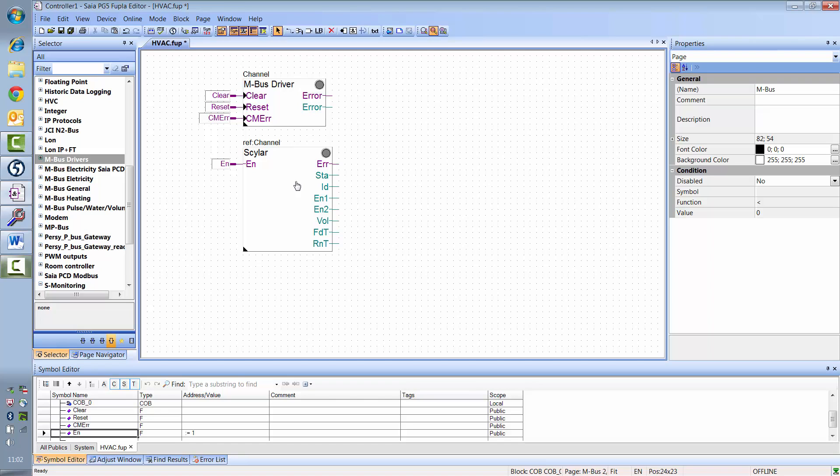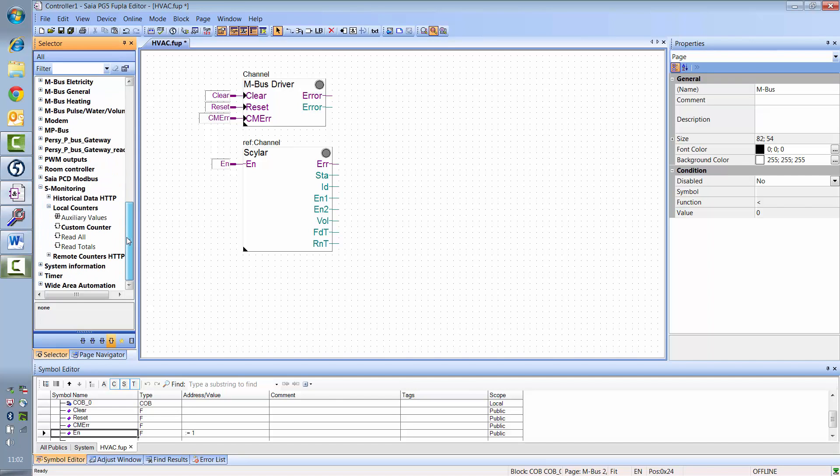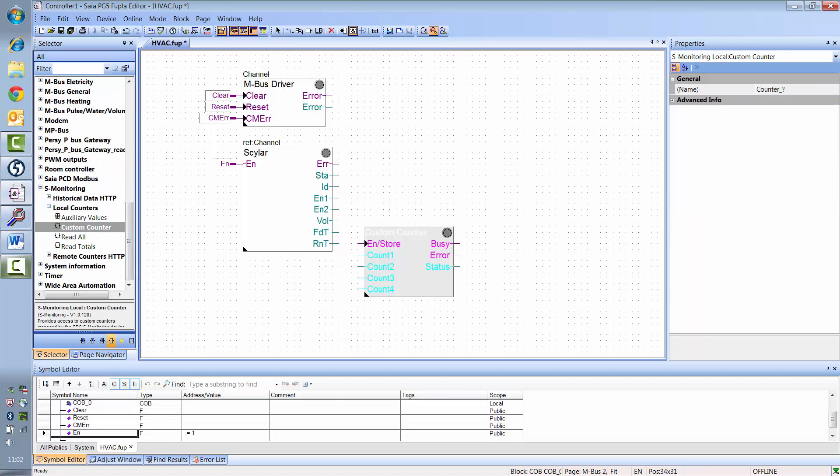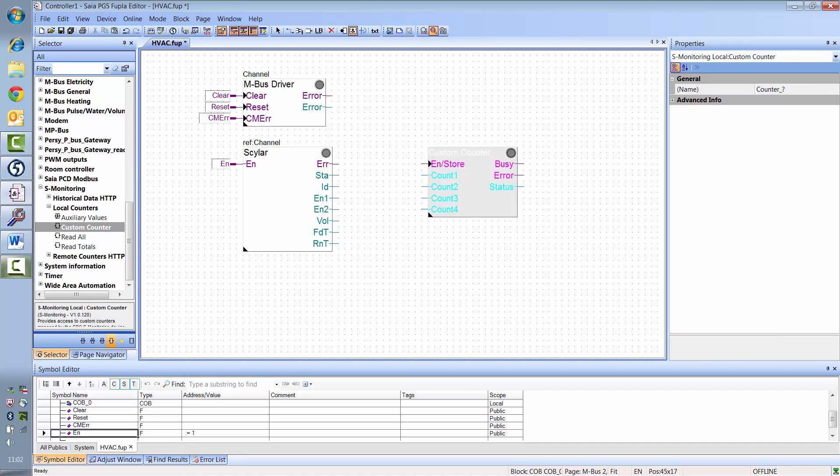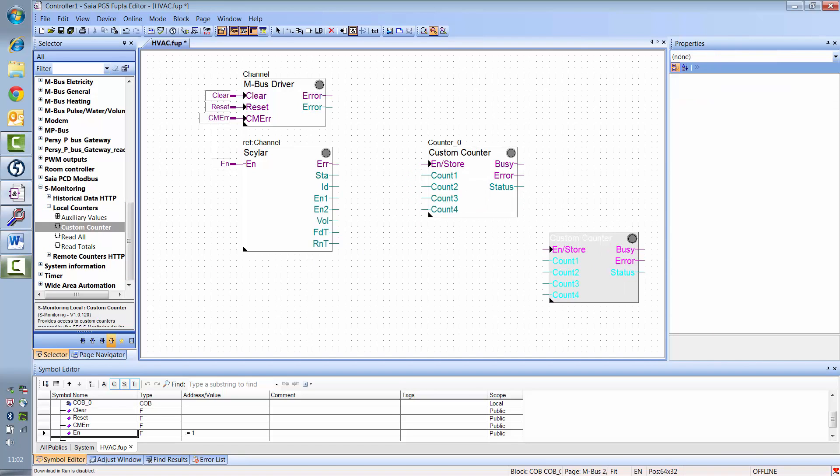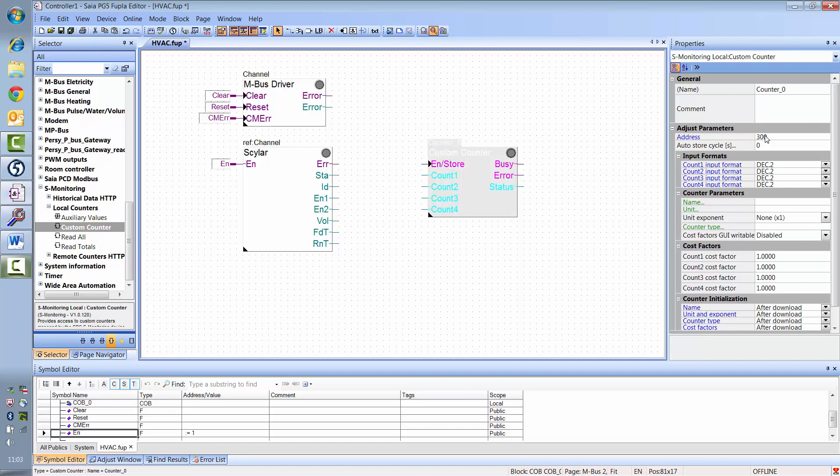For this, S-Monitoring lets you add virtual counters, which the program treats like S-Bus meters. To do this, add the custom counter F-box. In the custom counter F-box, you also have to set a unique address, like with M-Bus meters. The permitted address range is from 300 to 550.